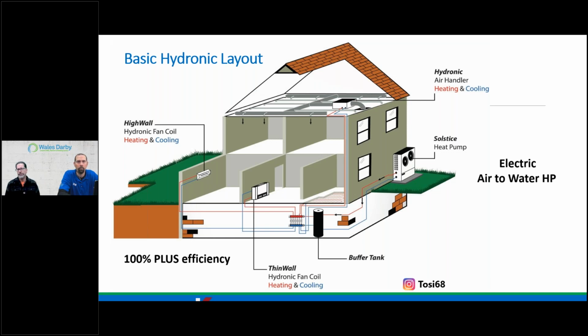The outdoor unit, right? There's our heat pump. We have different ones we can offer, different sizes, but both heating and cooling, low temperature heating. The buffer tank really becomes our source for the building. That's the vessel, that's the storage. It's an open vessel. It's just 4 tappings at minimum, but there's 2 tappings for the outdoor source or heat pump, and then 2 tappings to feed anything inward to the building or the space. So we are really concerned about just maintaining the temperature in that tank, using that as a battery and drawing that down as we get calls from different zones, right?